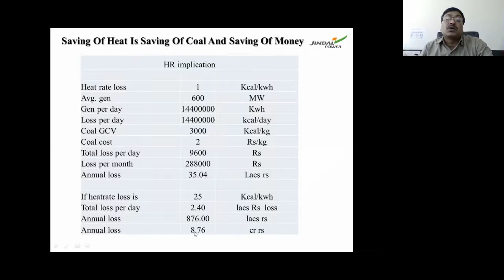On simple close monitoring, we can save not only 1 kilocalorie but a lot more, amounting to 25 to 30 kilocalorie per kilowatt hour. There is one more calculation: if you save 25 kilocalorie, it will amount to annual savings of 8.7 crore rupees for a 600 megawatt unit.